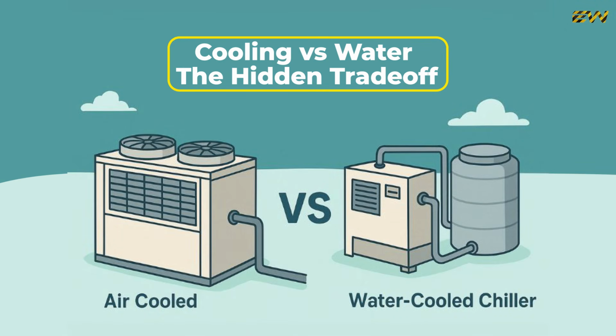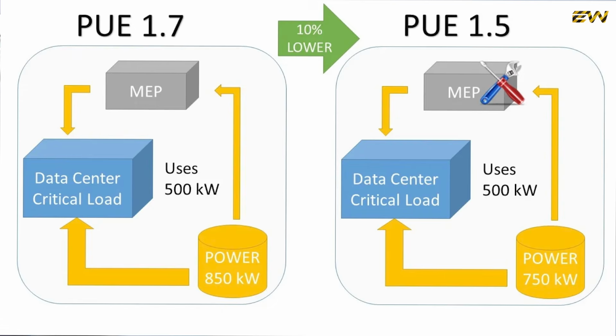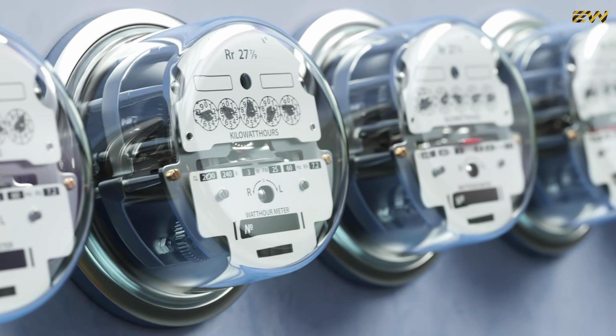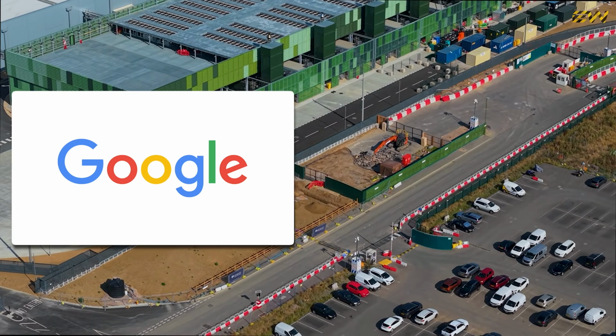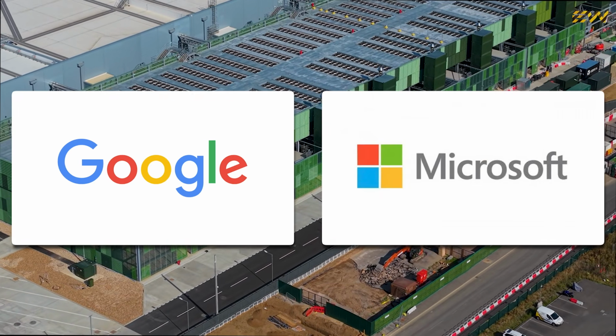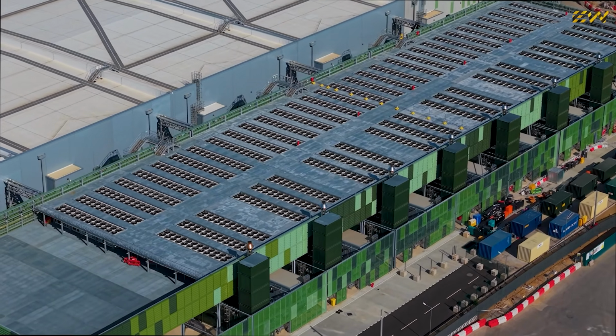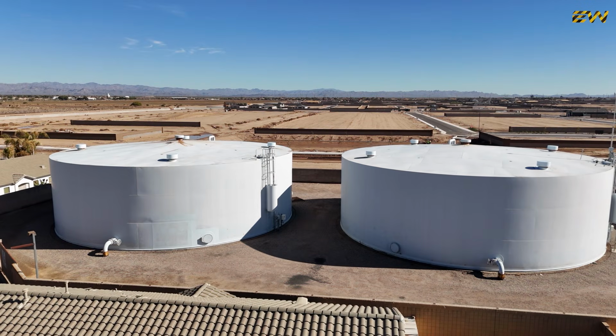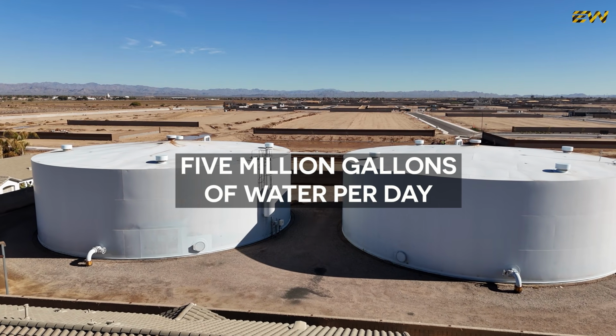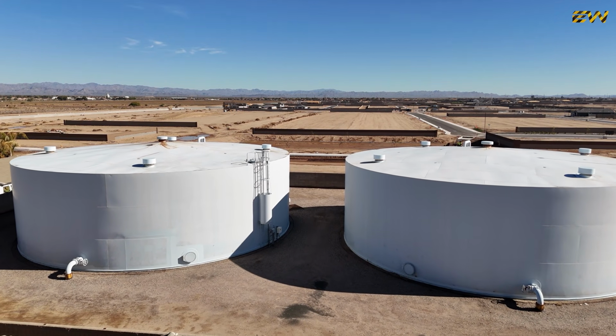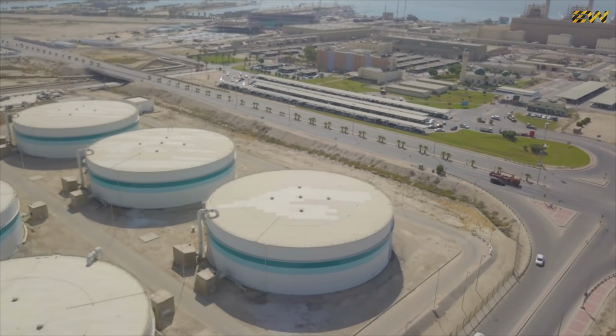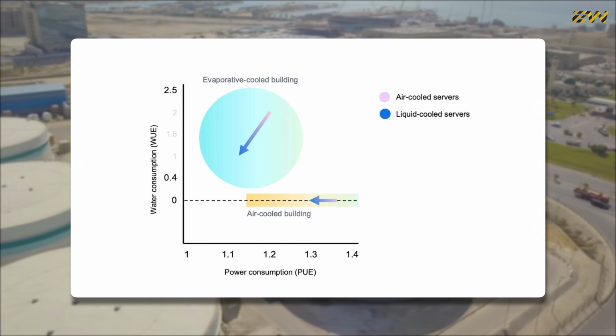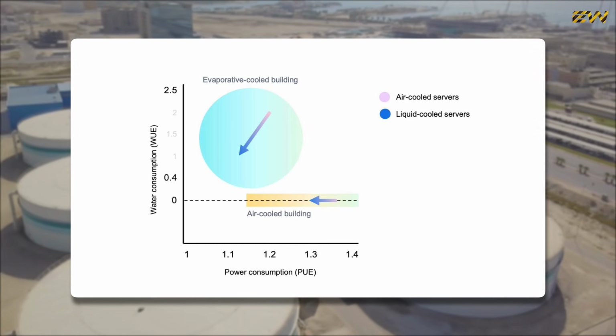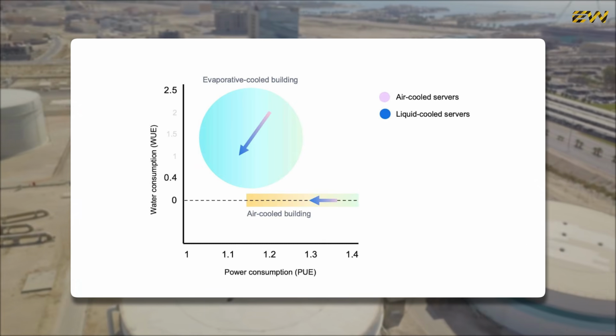Cooling versus water, the hidden trade-off. Efficiency is measured using power usage effectiveness, or PUE. It's the ratio of total facility power to power used by IT equipment. The global average PUE, around 1.80. Hyperscalers like Google and Microsoft report PUE values as low as 1.06. Impressive. But achieving that often relies on evaporative cooling. Large data centers can consume up to 5 million gallons of water per day, equivalent to a town of 50,000 people. Water usage effectiveness, WUE, becomes the trade-off. Low PUE can mean high water stress. So the energy problem becomes a water problem.